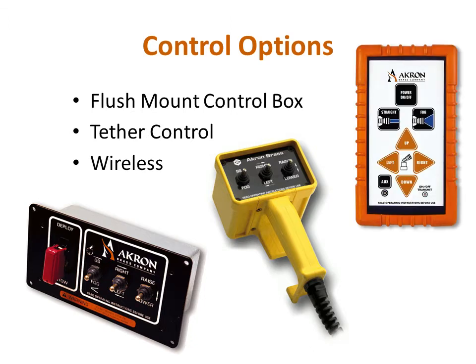Another option is the wireless remote control. This allows the operator to move freely about the apparatus while operating the monitor. This unit has controls for the monitor and nozzle like the tether controller, but also has an auxiliary button that can be assigned to either stow or deploy, but not both. These controllers are arranged in the order of increasing complexity they add to the system, and depending on which are used, may require slight modification to the troubleshooting process when looking into a problem.